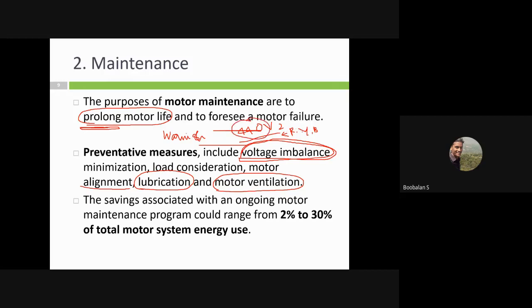Sometimes Y to B phase comes around 350. If R to Y comes as 440, Y to B as 390, and B to R as 350, what does this mean? The motor winding is getting some leakage, so there's an issue in the winding and we need to stop this motor. This is called voltage imbalance, which we'll see later.